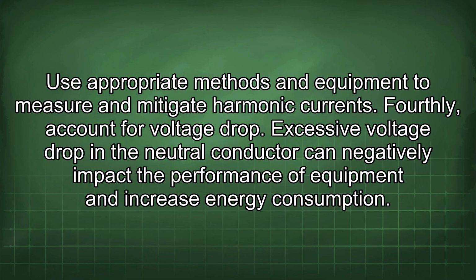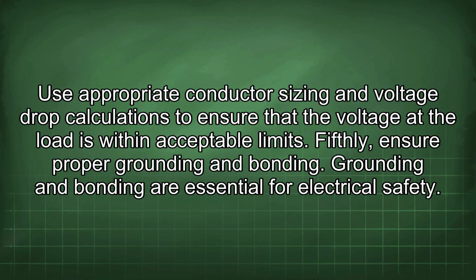Fourthly, account for voltage drop. Excessive voltage drop in the neutral conductor can negatively impact the performance of equipment and increase energy consumption. Use appropriate conductor sizing and voltage drop calculations to ensure that the voltage at the load is within acceptable limits.